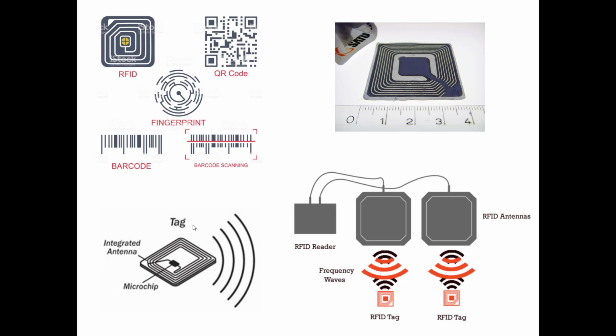For example, in medical centers we have around 10,000 medical devices in the PM program, or preventive maintenance schedule, which need to be located on the date of performing the maintenance. This sometimes will be difficult because we have a large number of medical devices, and we have large areas in the hospital or the medical center.